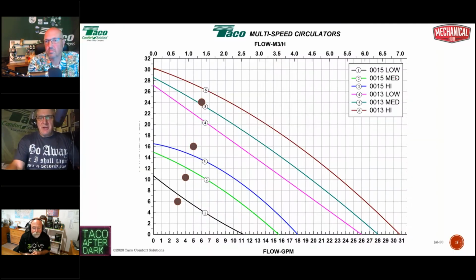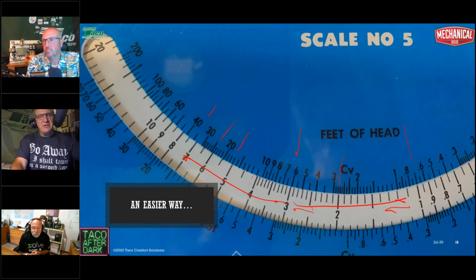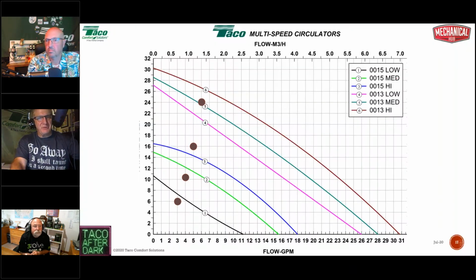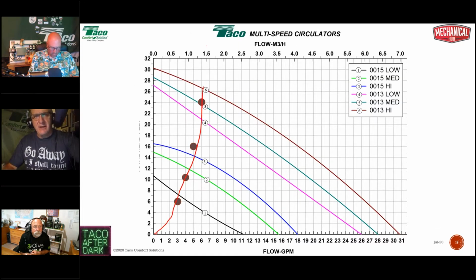Okay, so I know them all. I know all these points on the system curve. Now, once I know them, I can put them on a pump curve, a pump performance curve, and see what happens. I can plot out these points. Everything starts at 0. And I simply connect the dots. Close enough. We connect the dots, and then we see where this system's actually going to work.